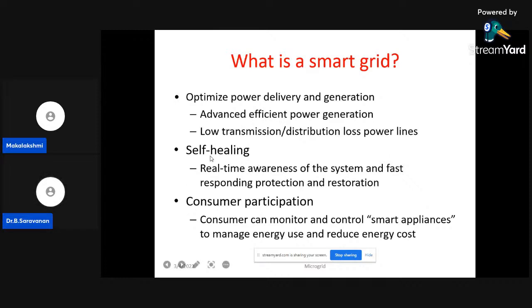Self-healing is important - real-time awareness of the system, fast responding if there is a fault. As I said, if something goes wrong, we can find which circuit breaker tripped and the history of the fault within a second after it happens. Sometimes the grid itself will heal and come back to normal - it restores on its own if it's a minor fault. If a major fault is recorded, it gives an alarm to the operator to attend to that particular transmission line or generation.